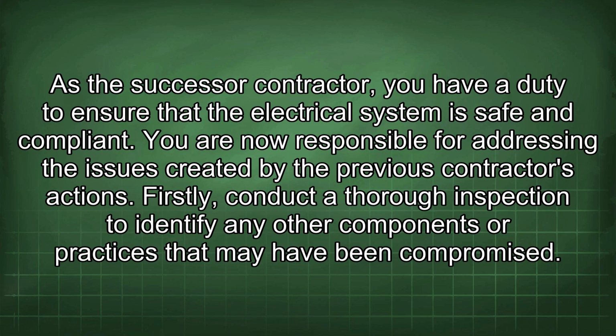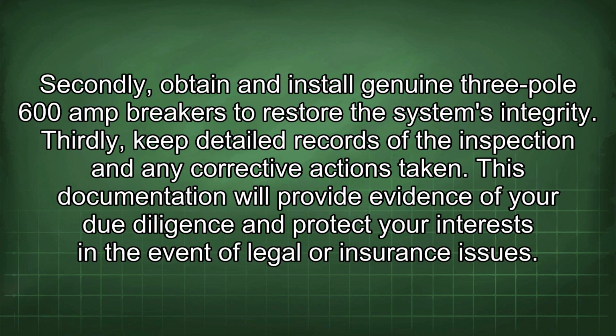You are now responsible for addressing the issues created by the previous contractor's actions. Firstly, conduct a thorough inspection to identify any other components or practices that may have been compromised. Secondly, obtain and install genuine 3-pole 600 amp breakers to restore the system's integrity. Thirdly, keep detailed records of the inspection and any corrective actions taken.